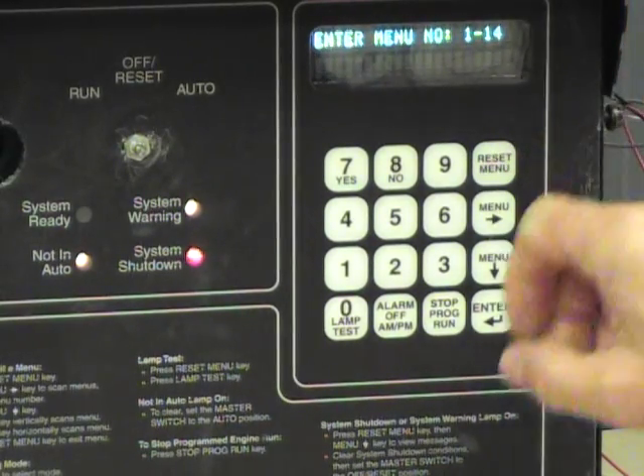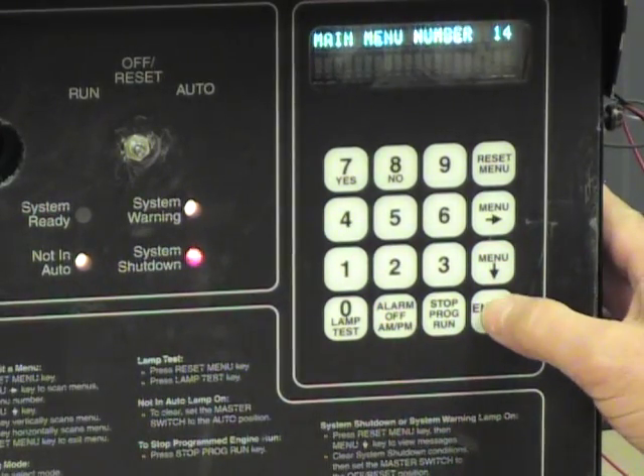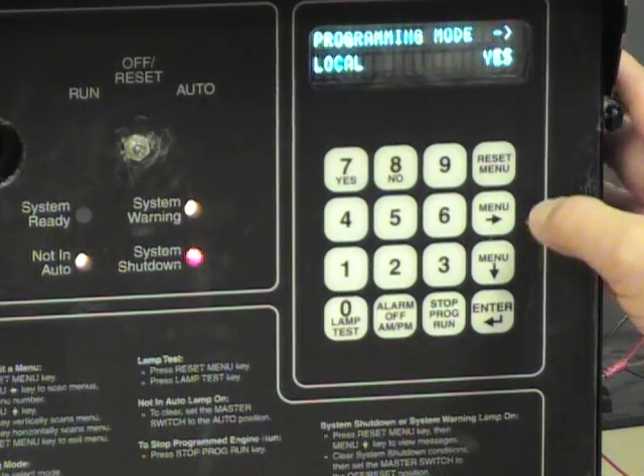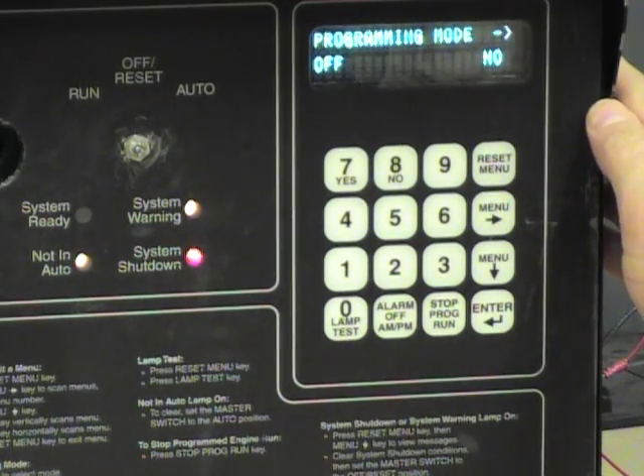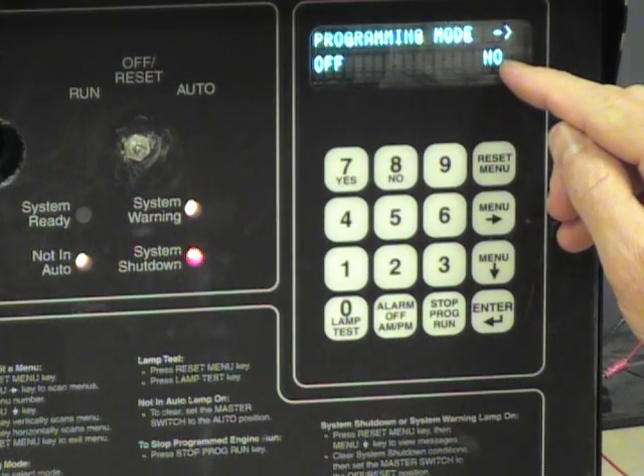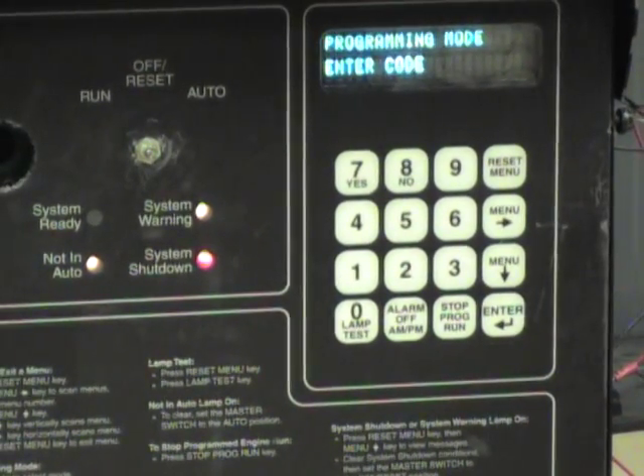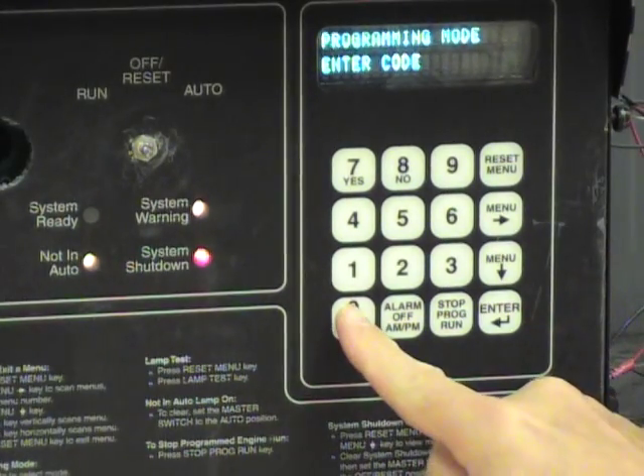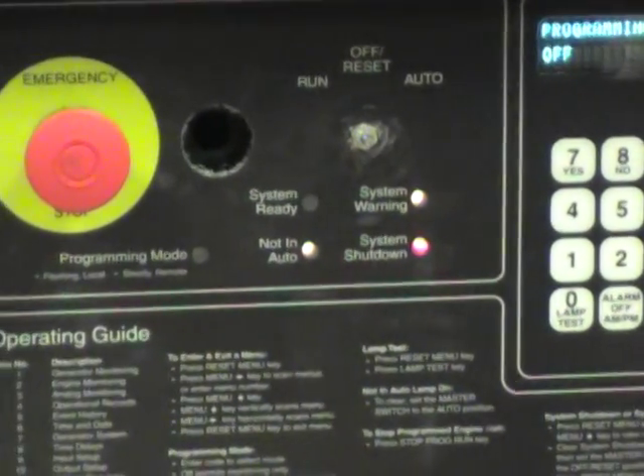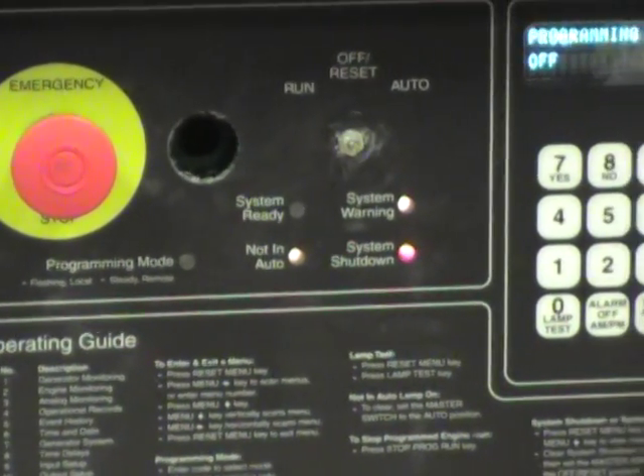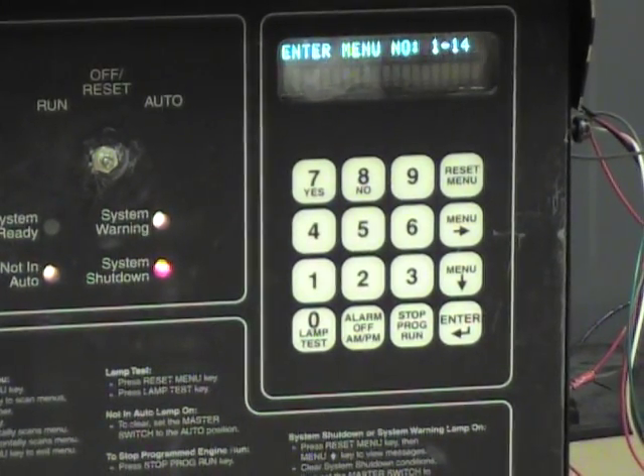Let's hit reset menu and go back to menu 14, programming mode, so that we can leave programming mode. I hit 14 and enter and go down one step. We will use the right arrow until we get to programming mode off. Right now it is showing we are not off, but we want it to be, so I am going to press yes and then enter. It asks once again for the password — zero — and enter. It says entry accepted. The programming mode LED has stopped blinking. We hit reset menu and we are back to where we started, but now we have Modbus enabled. That is it.